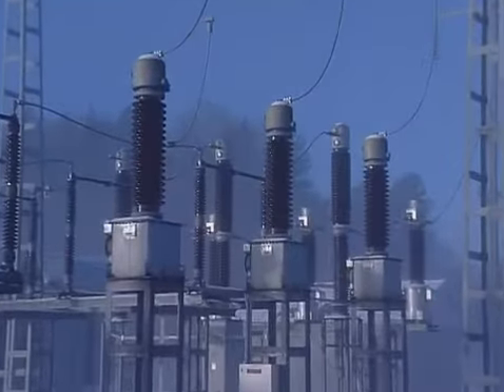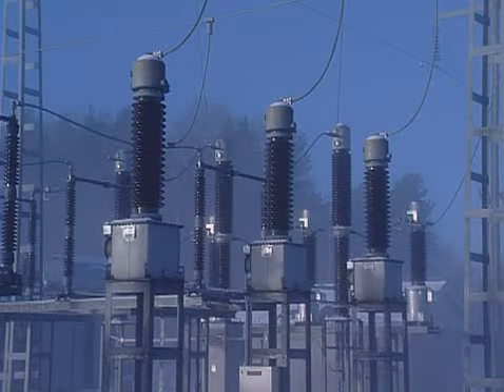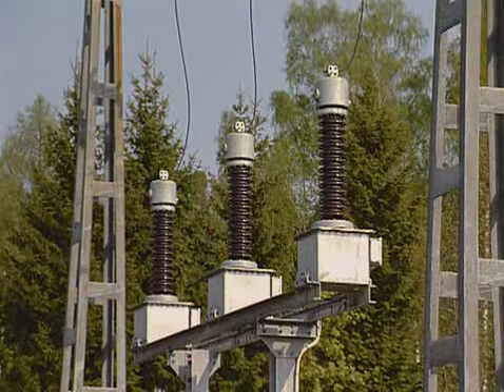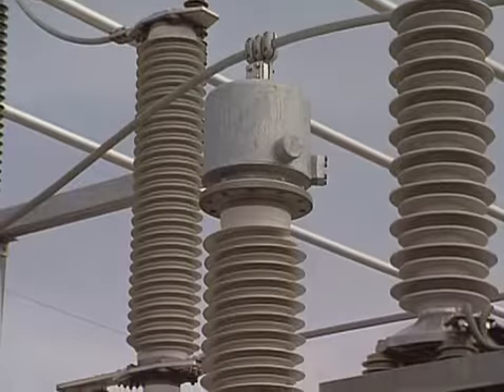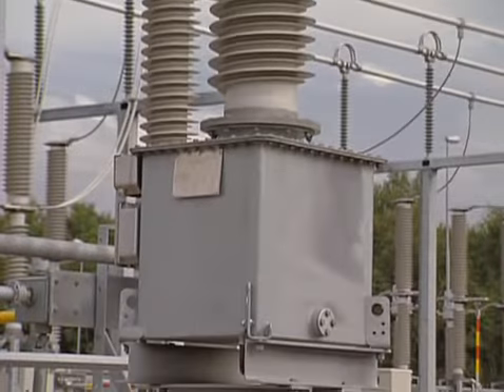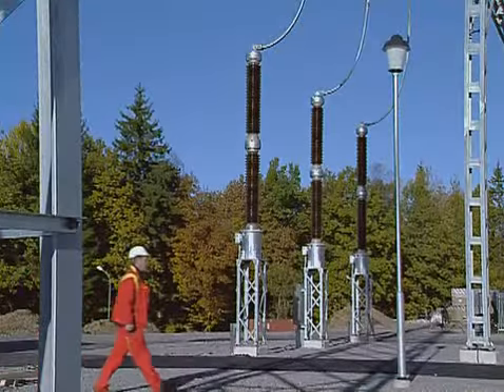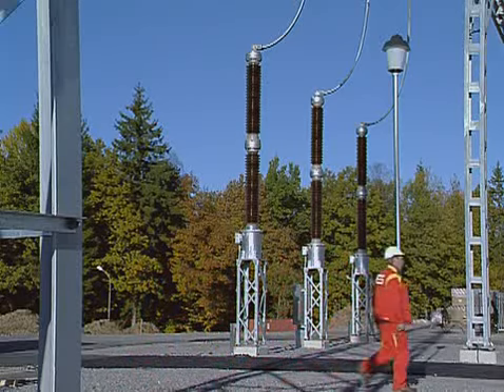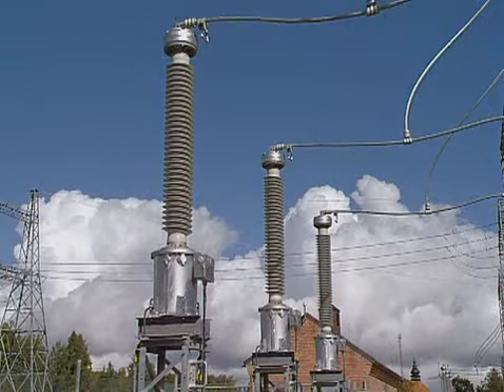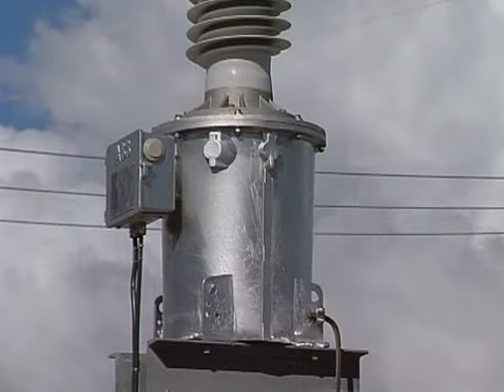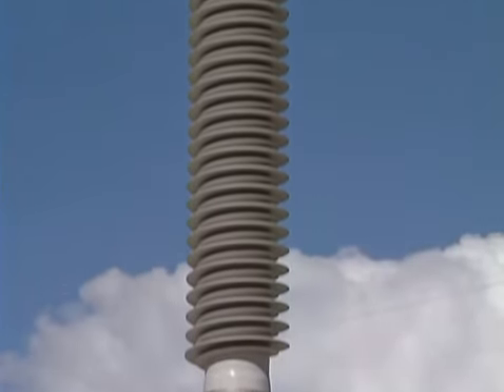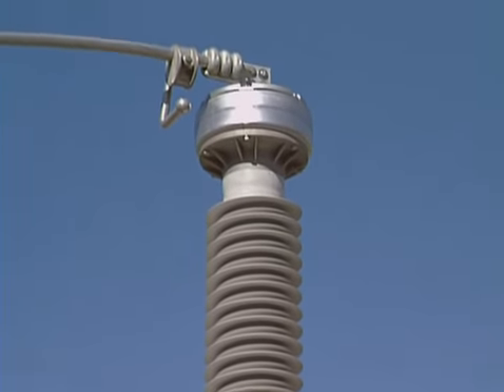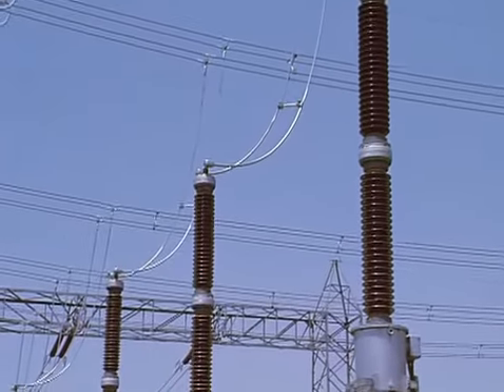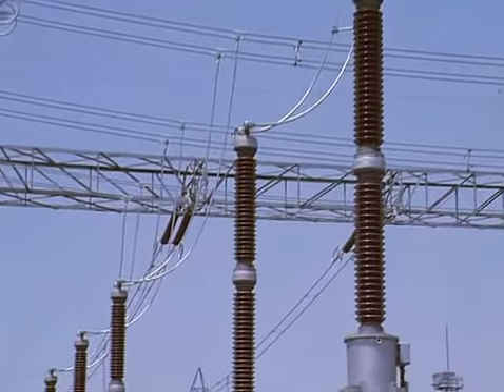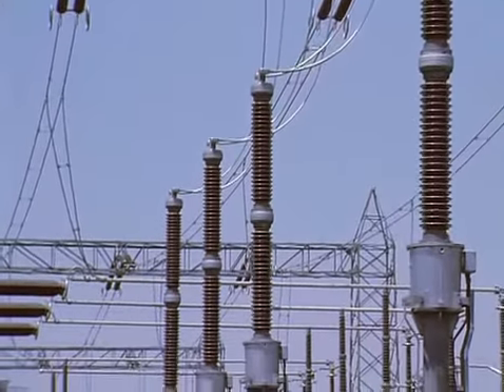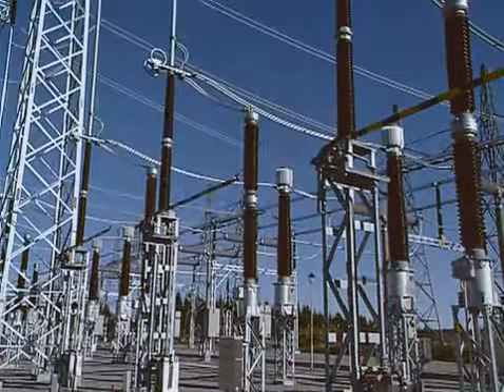The EMF inductive voltage transformer also holds the #1 position in worldwide sales in the oil-insulated voltage transformer range. It is designed according to the same basic concept as the current transformer. ABB was the first in the world to manufacture capacitor voltage transformers. They are constructed with an inductive part and a capacitor part, in which the capacitor works as a voltage divider. For high voltage, several capacitors are connected together. Thanks to a mixed dielectric, a dependable reading is ensured during all types of operational conditions.